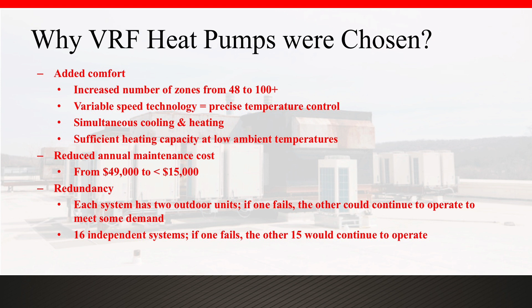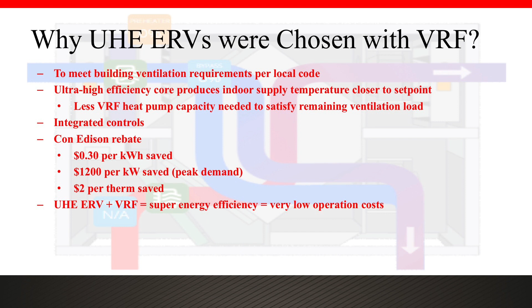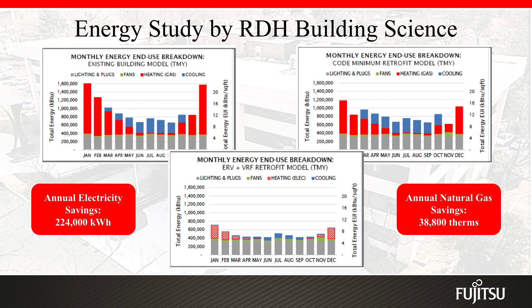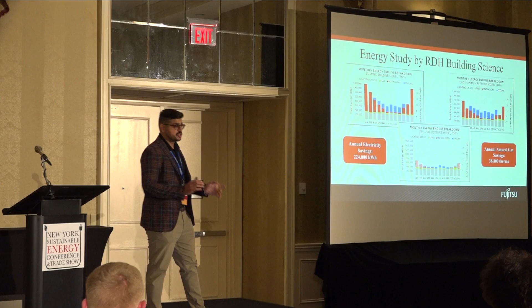Okay, maintenance costs reduced significantly. Redundancy, one unit fails, the other 15 are still going to continue operating. Okay, ERVs were chosen because you need fresh air, and ultra-efficient ERVs combined with VRF is just a win-win scenario all the way around. Okay, what are we talking about when we say win-win? This is the current building energy consumption, okay, with the old systems, right? Red represents natural gas. If you replace it with like-to-like code minimum rooftop systems, it will go down to something like that. If you replace it with ERVs plus VRF, you reduce natural gas completely, replace it with cooling, but even then save 224,000 kilowatts in cooling and 38,000 therms in heating.